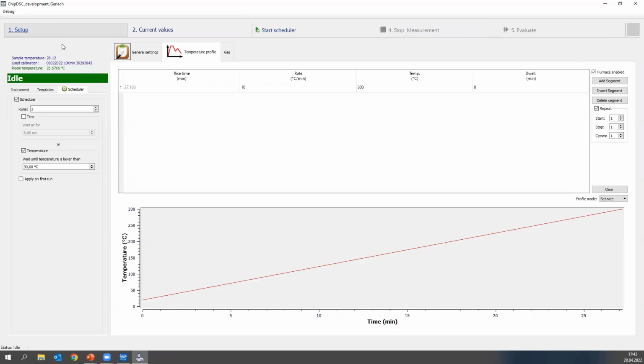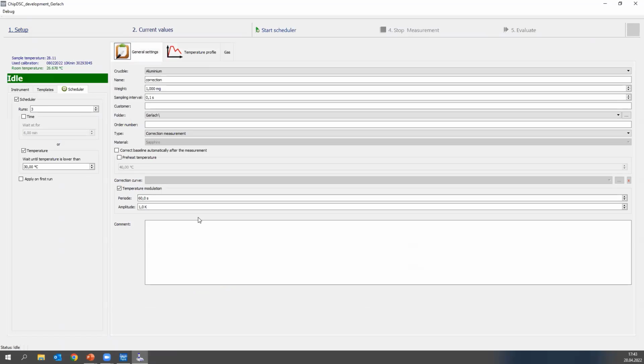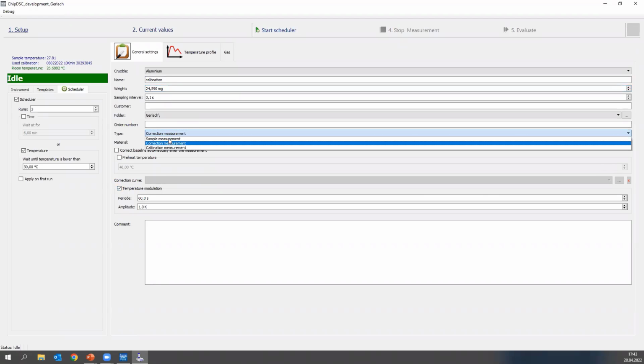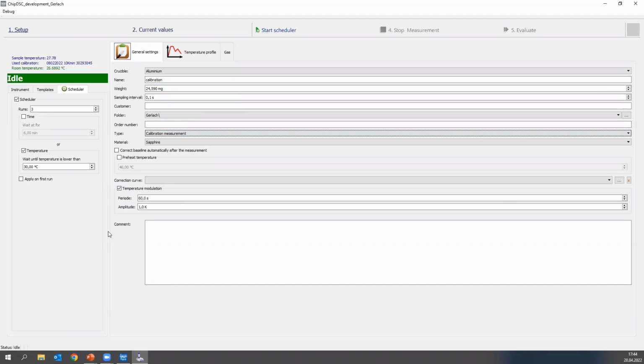Of course, I would like to stop this measurement and go on with the calibration. What we have to change here is, of course, the name. Let's call it calibration. Now we have to insert the right value very precisely. For example, it's a 24 milligram sapphire, or a 24.59 milligram sapphire. And we have to change it here to a calibration measurement.